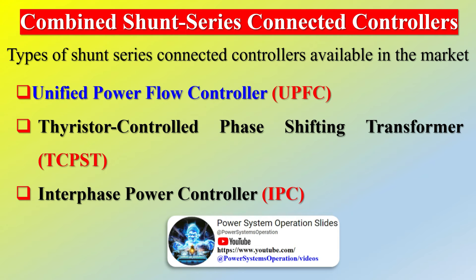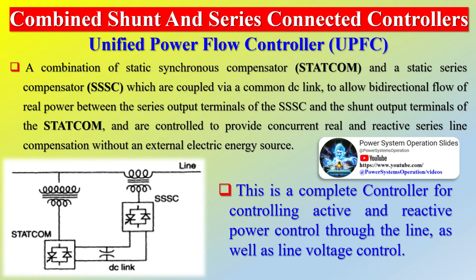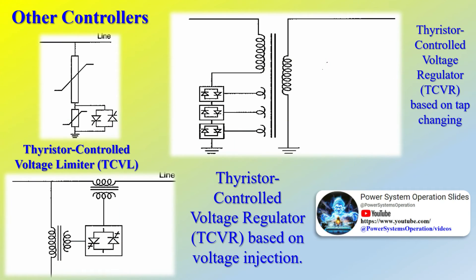Regarding the choice of controller: a series controller controls current and power flow by controlling the driving voltage. To control current/power flow and damp oscillations, a series controller is several times more powerful than a shunt controller. A shunt controller injects current into the line and is used for more effective voltage control and damping voltage oscillations. Injecting voltage in series with the line can improve the voltage profile, but the shunt controller is more effective at improving the voltage profile at the substation bus. For a given MVA, the series controller is smaller than the shunt controller. Shunt controllers cannot control power flow in the lines, while series controllers must bypass short-circuit currents and handle dynamic overloads.